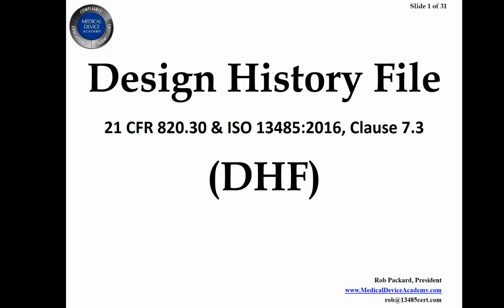Okay, the regulation specifically for a design history file, it's the last subpart of 21 CFR 820.30, and it's J is the subpart.